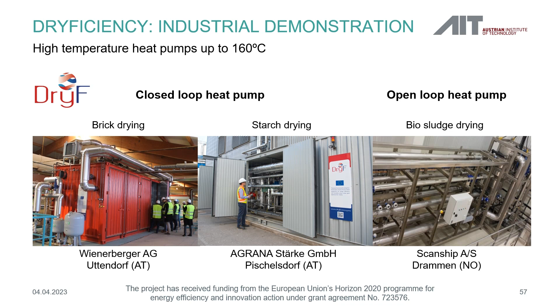Here you see the operation experience we've gathered with the closed loop heat pumps. In this diagram, you see the temperature lift on the x-axis and the COP on the y-axis - the heating COP, which is the heat delivered by the heat pump versus the electricity consumed. With the two demonstrators, we tested the whole range of what's possible with these plants, successfully collecting about 8,000 hours of operation.